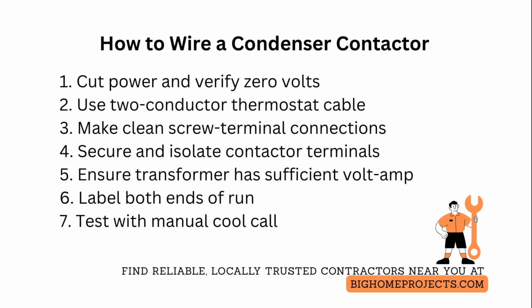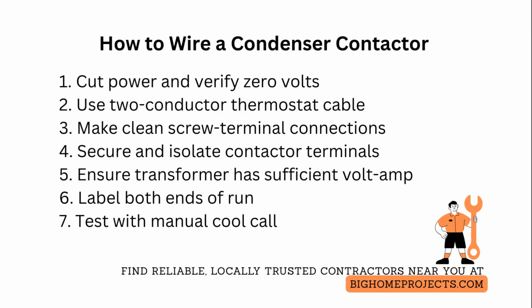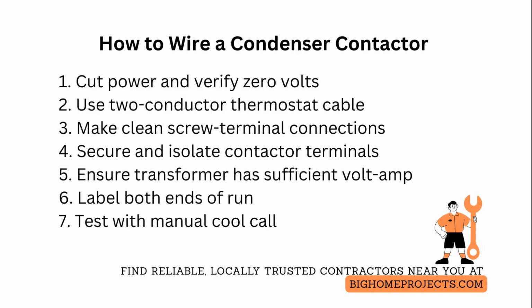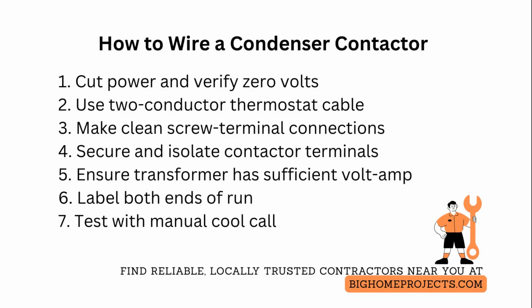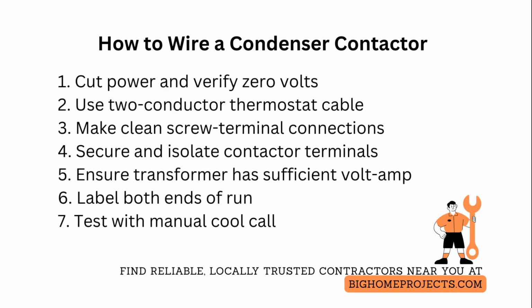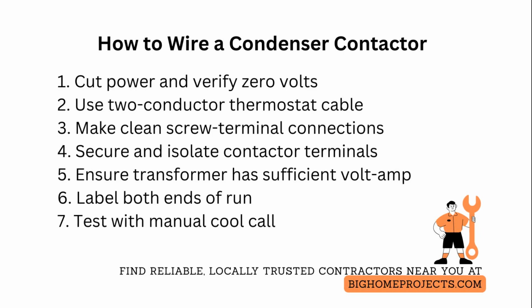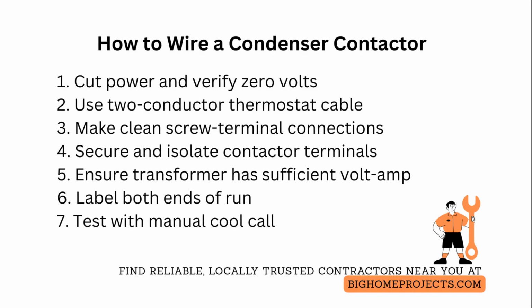When using a common from the control board, ensure that the board's transformer has sufficient VA capacity for additional accessories. If you add accessories and the transformer is undersized, swap to a higher volt-amp transformer rather than piggybacking external transformers. Label both ends of the run at the board and at the condenser with circuit and zone identifiers to speed future service and reduce miswiring risk.